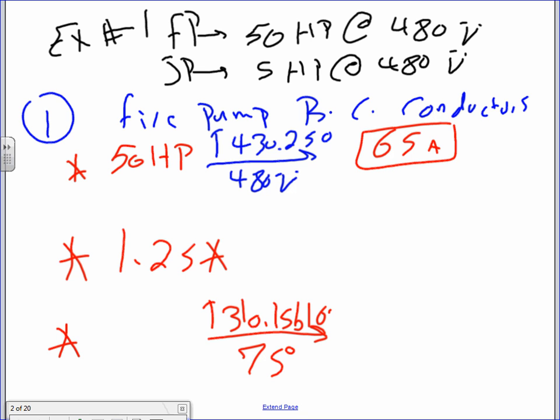65 amps. So you're going to go to this table and find the full load current. You have done that before. It's nothing new. You're going to find the full load current for the 50 horsepower from the NEC code book. You do have this one in front of you, so expedite the process. Then you multiply 65 by 1.25, and that will get you 81 amps.